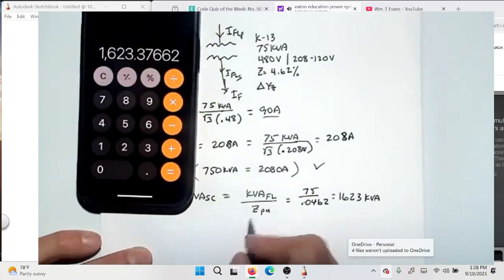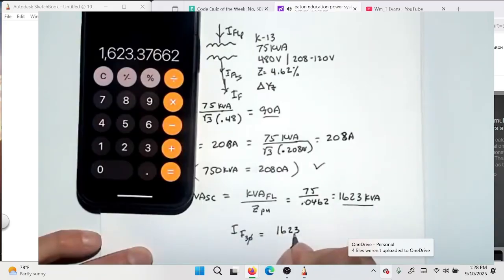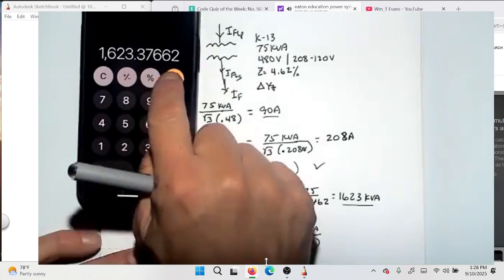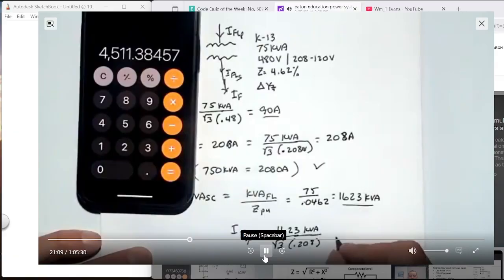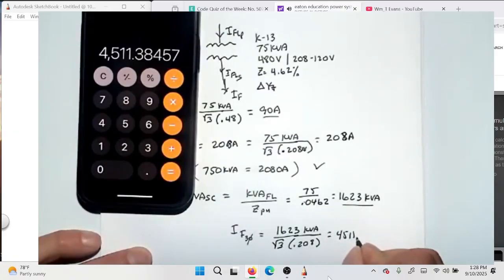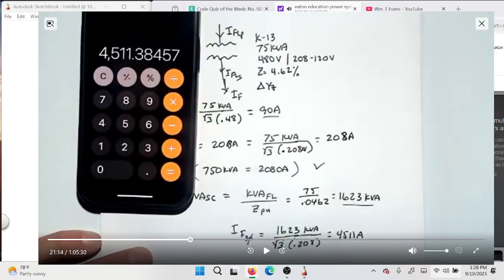Then for I fault three phase, we take our short circuit kVA, which is 1623 kVA, divided by the square root of 3 and divided by 0.208 kV, and we end up with about 4,511 amps of fault current. Already got that? So far, so good?